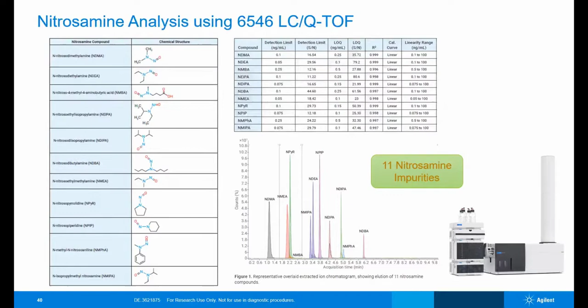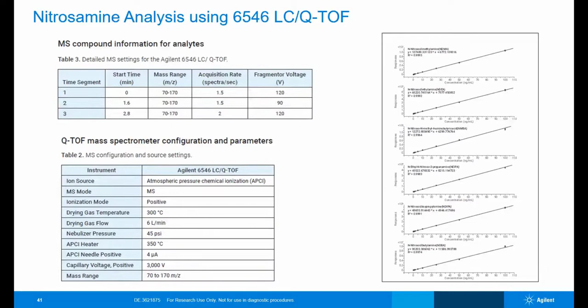And you can see the LOQ levels here. Again, these LOQs are better than what FDA's document is talking about. Again, we made use of diverter valve program to plan the experiments, and you can see excellent recovery linearity curves here, and source parameters for these experiments are kept same as we used in LC triple quad scenario. If we see this slide, then we would realize that even at the concentration of 0.1 nanogram per ml, we have the consistency of results, which gives best-in-class result in terms of reproducibility.